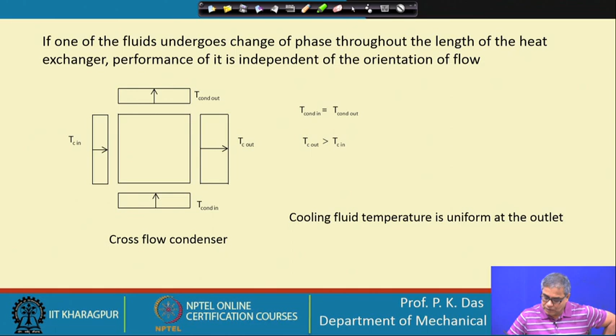So, obviously you see that there could be other reasons for selecting the arrangement, whether we will go for parallel flow, counter flow or cross flow for a phase change heat exchanger, but thermally all of them are equivalent. There could be other mechanical reasons, there could be that we have to accommodate more amount of tubes etcetera. So, other plant related reasons could be there, but thermally they are identical. Cooling fluid temperature is uniform at the outlet. So, this is one very important observation.